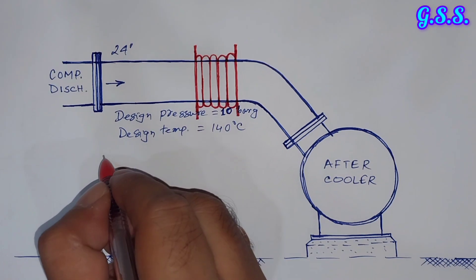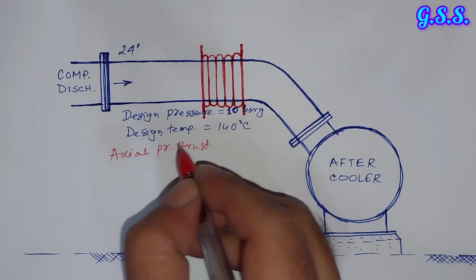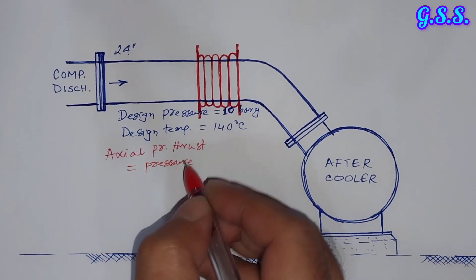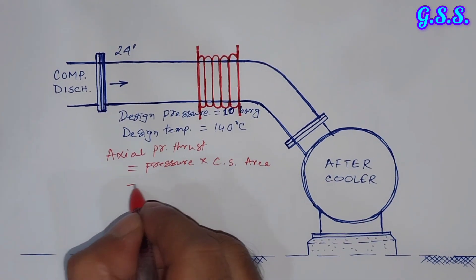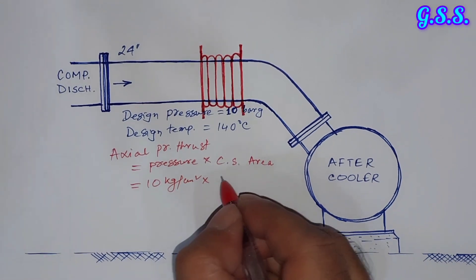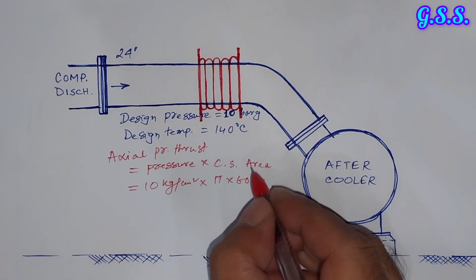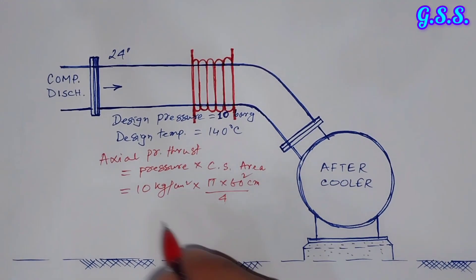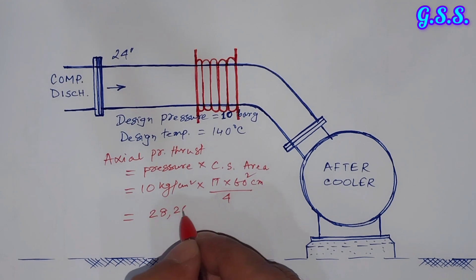That axial pressure thrust will equal internal pressure multiplied by the cross-sectional area of the pipeline or of the bellow. That means 10 kg per cm² multiplied by π times 60 cm ID of the pipeline — since the diameter is 600 NB — divided by 4. This equals 28,260 kg.